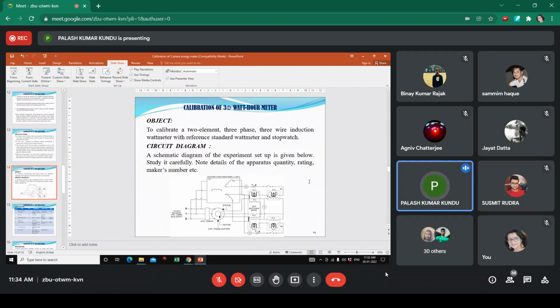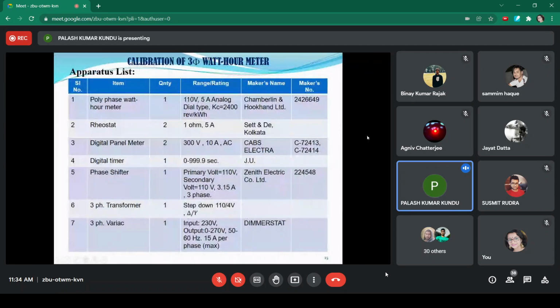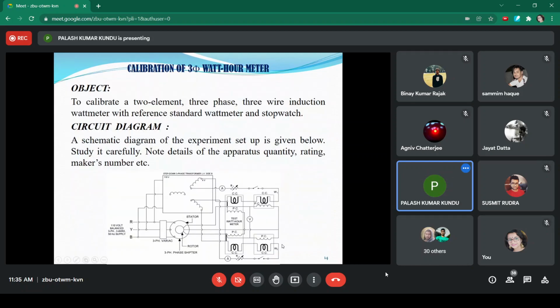So this is the experimental circuit diagram, and these are the apparatus which are generally required for carrying out the experiment. So 7 types of items are used: polyphase watt-hour meter, that is the test watt-hour meter, two rheostats, digital panel meter for voltage measurement, phase shifter, three-phase step-down transformer with delta-star connection. The secondary is connected in star and the primary is connected in delta, because the supply system is a 3-wire system, and the 3-phase variac. The variac is not shown here.